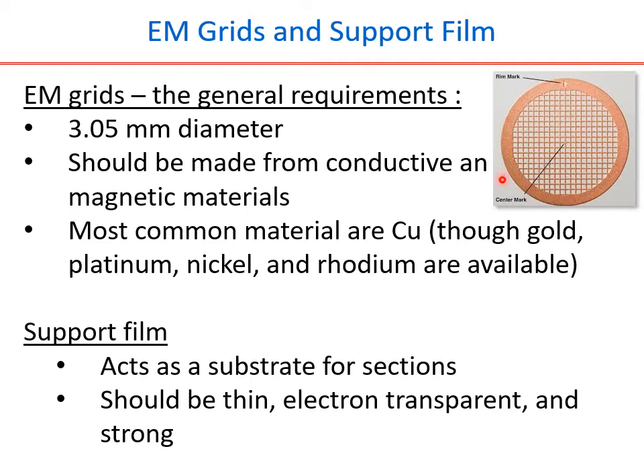You know the consequence of capturing the image of a moving object. The entire cause for this is the heat generated. So in order to minimize this kind of drifting, we need to minimize the heat generated here, and that will be done again by the thermal conductivity of the metal that you are taking. Any heat generated because of the bombardment of the electrons on the grid bars will be carried away outside the electron microscope grid. So the electrical conductivity and thermal conductivity of the grid are well taken care of here. That is the reason any grid should be made from a conductive material.